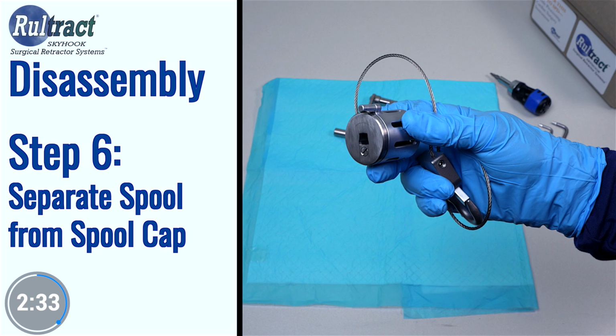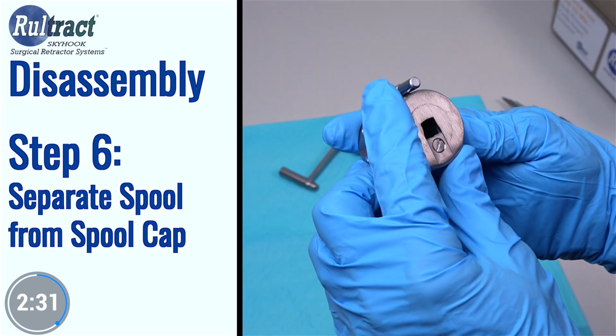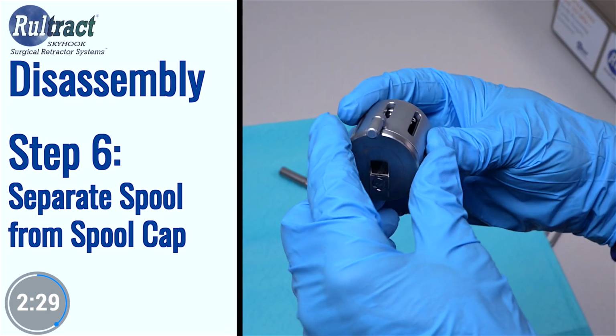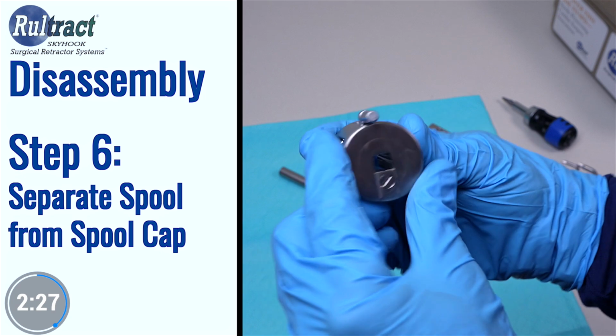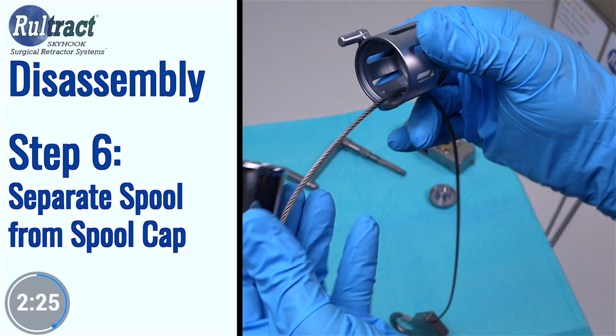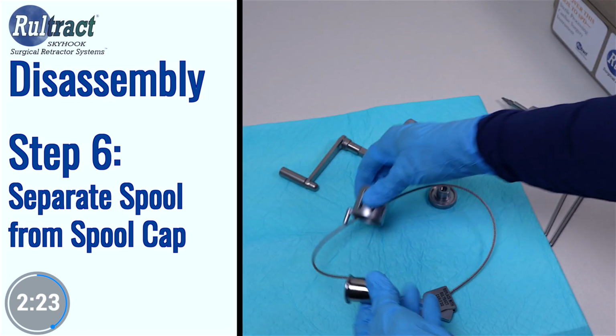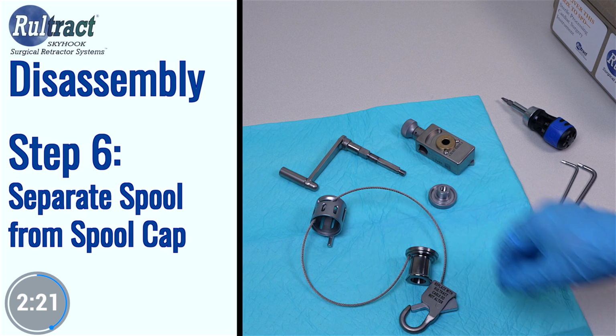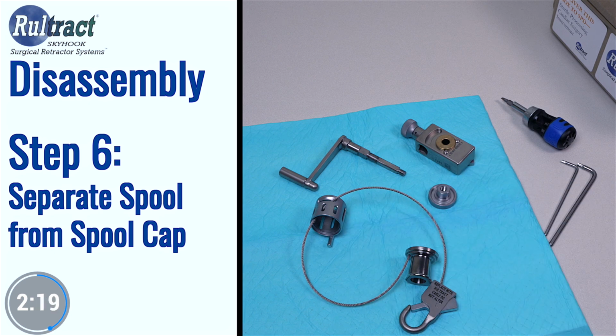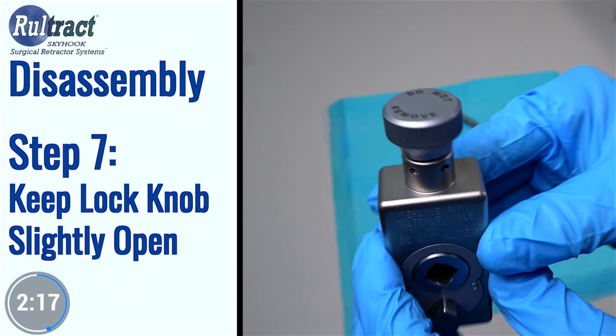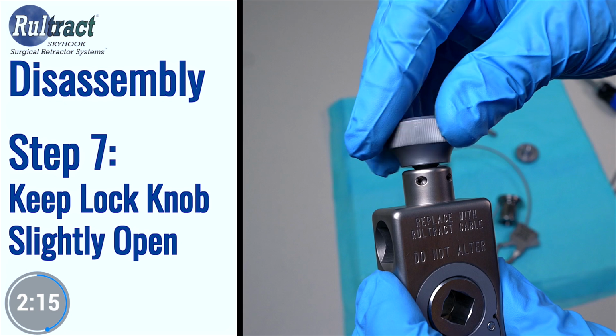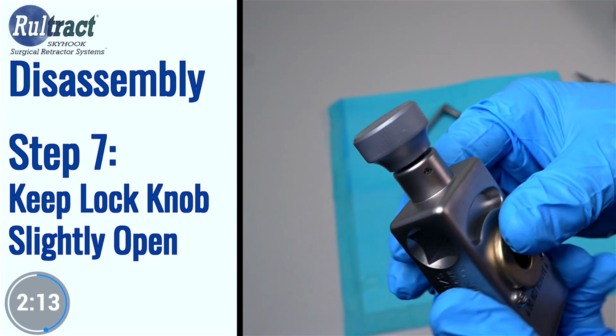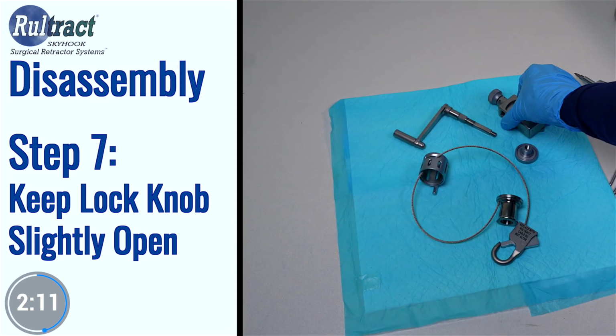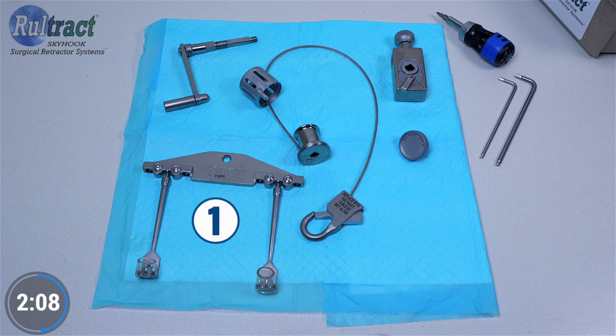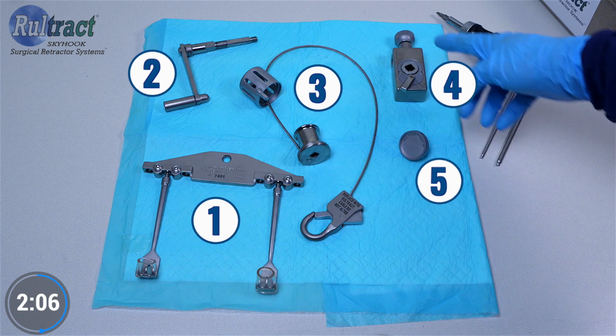Next, separate the spool from the spool cap. To do that, align the cable access plate screw with the pin and the groove. When you line up the pin, the screw, and the groove, they'll just slide right apart. No further disassembly is required of these pieces for cleaning and sterilization. Be sure that the lock knob is not closed all the way or opened all the way. Keep it somewhere right in the middle so that it has some play in it. The disassembled Rultract Ratchet Rake assembly is in 5 pieces and ready for the cleaning cycle.